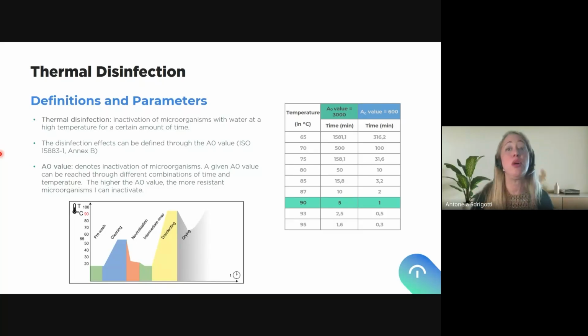And this is what I try to show you on this table. Here you have temperature and a certain A0. Just two examples of the most used A0 values in the market. This 600 is the minimum one for critical devices, for critical instruments. And highlighted in green, you have the most used. So 90 degrees nowadays, or 93, but 90 is the most widely used worldwide, in a higher percentage of the machines. And in just 1 minute, I can reach the minimum level of disinfection, the ISO standard and the classification of the medical devices intends to have when performing a thermal disinfection inside a washing machine.